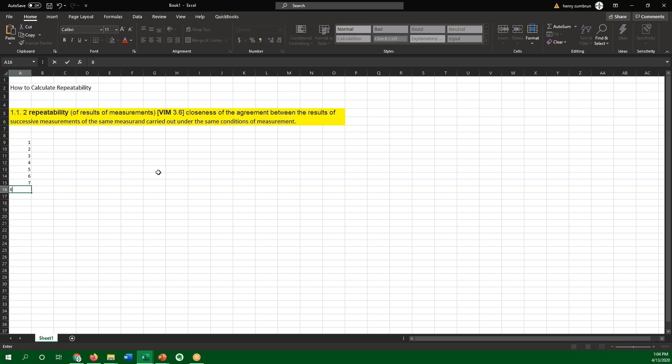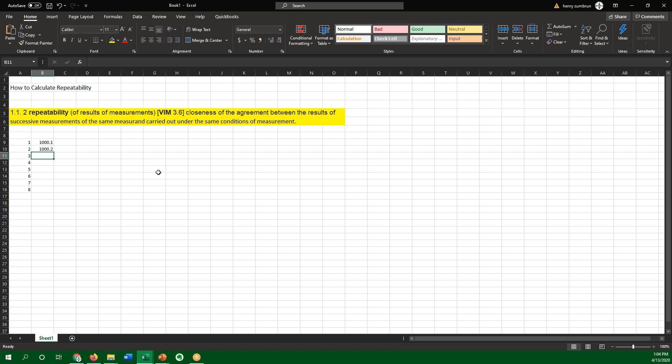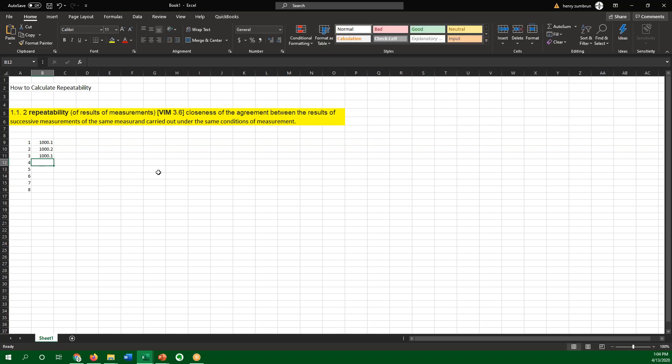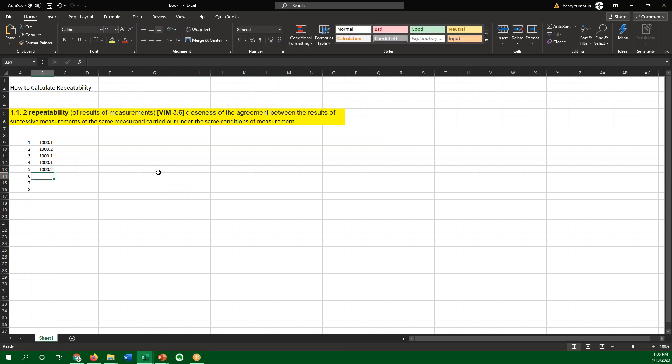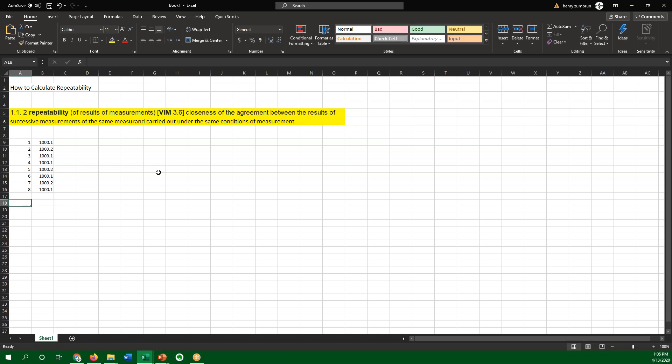But simply here, if we had, say, eight trials in a force measurement, because it's Morehouse and we do force, say we did a 1,000-pound instrument and the device had a resolution of 0.1. So if we looked at repeatability and we made successive measurements, 1,000, 1,000.1, 1,000.1, if we kept making these measurements and we looked at how to calculate repeatability here, I'm just typing in numbers we may see if we put a 1,000-pound instrument in a deadweight machine. So I took eight measurements here.